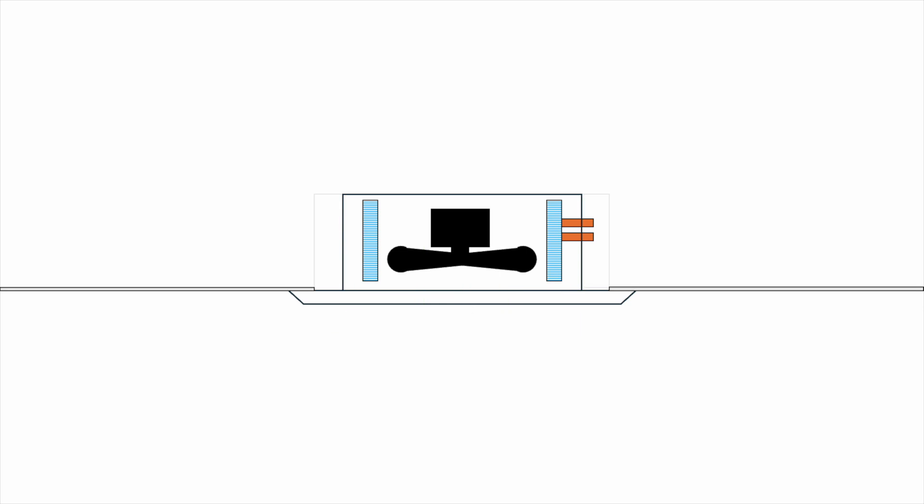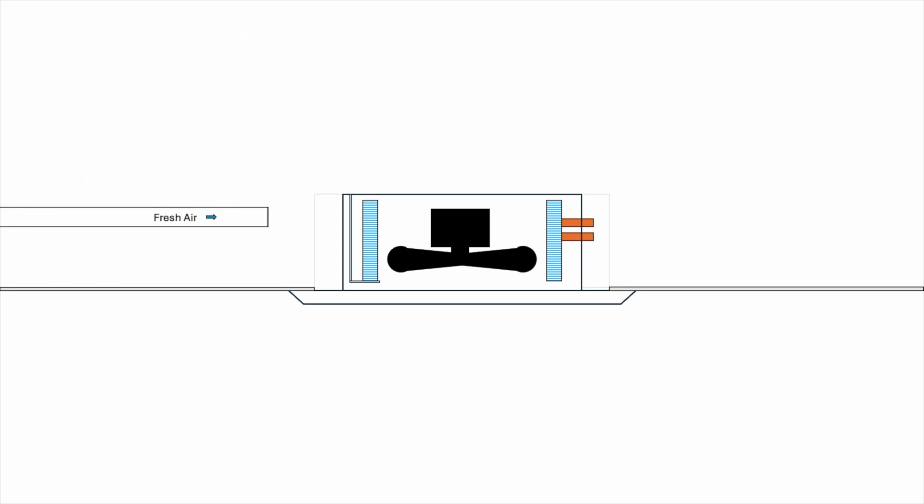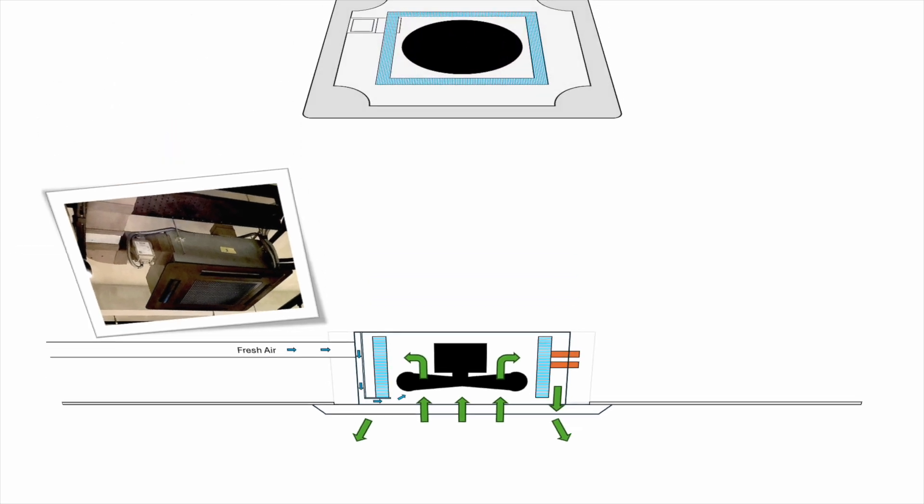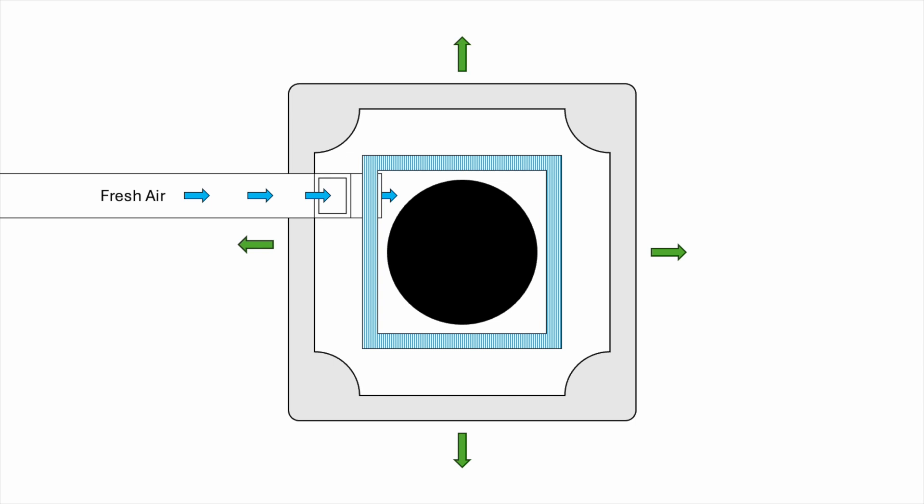One of the advantages of ceiling cassette units over wall-mounted units is the ability to introduce fresh air. Most ceiling cassettes have a channel for fresh air. On the outside, we can see these breakable panels. Once we open it up, we can attach a fresh air duct. The fresh air will flow into the ceiling cassette through the channel, mix with the return air and supply to the room. Let's look at it from the top. The fresh air comes in, mixes with the return air and supplies to the room.